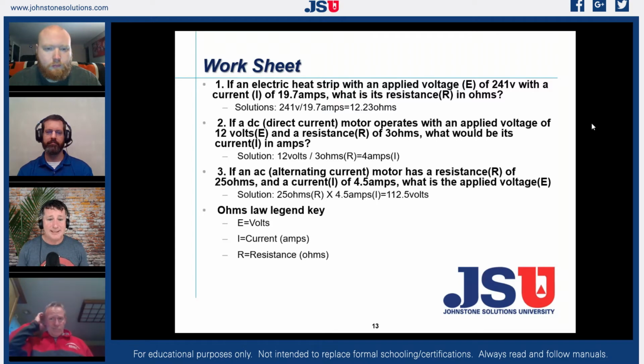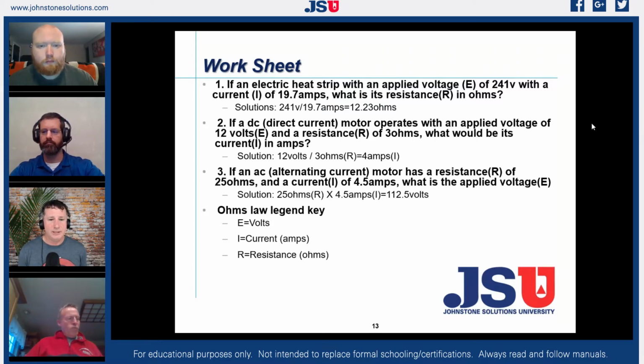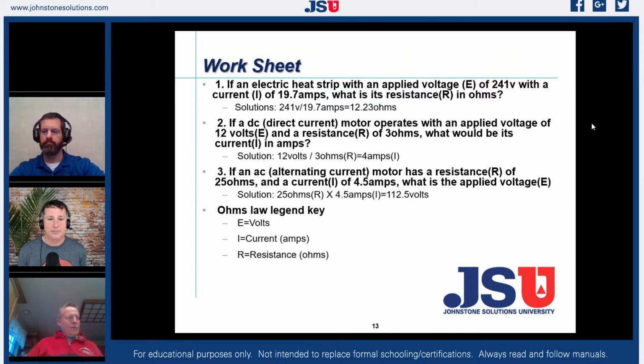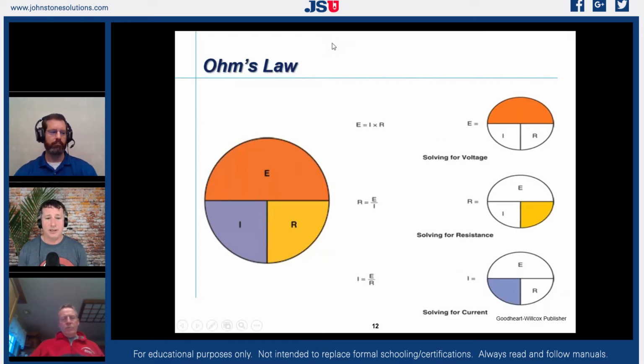And we can calculate exactly what the resistance is. If we take 241 volts applied to an electric heating element, then use our meter to check the current flowing through the conductors to that heating load and get 19.7 amps, we can simply plug those into Ohm's law. With volts and amps, I now have an exact resistive factor across that element.